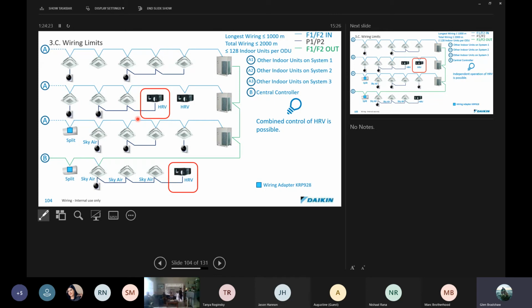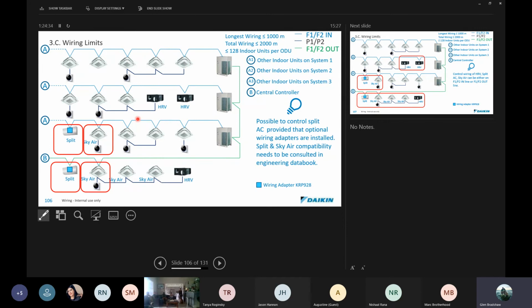We can connect up our ventilation type equipment onto there as well, VAM units. And Sky Air units can also be connected onto this. Sky Air units have their own F1, F2. In the case of this, the daisy chain would then run to the F1, F2 on the indoor, remembering that on Sky Air, the F1, F2, if they're going to use it, is merely a communication cable, just there for the centralized controller, and that is found on the indoor units.